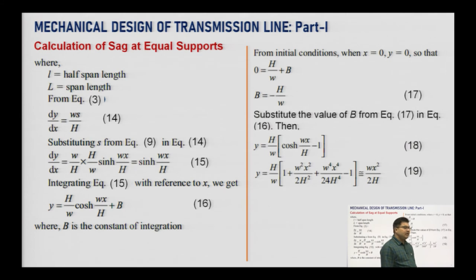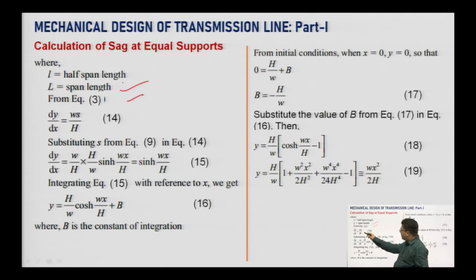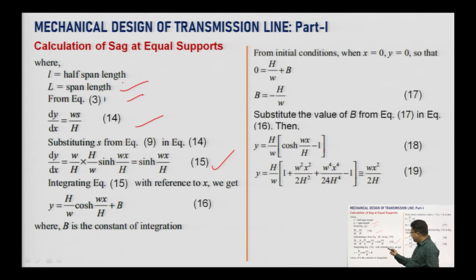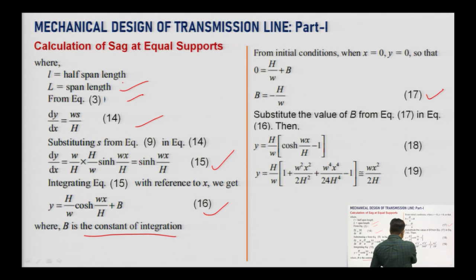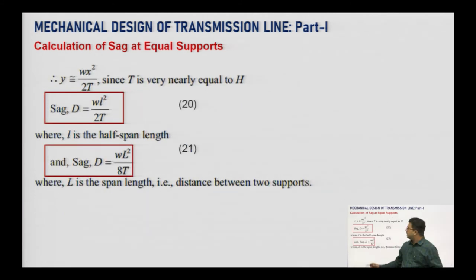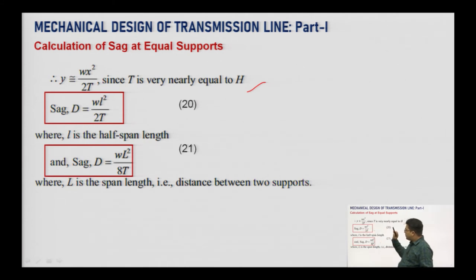From these equations, substituting and integrating with respect to x, we get y = w/(2H) · x² + B, where B is the constant of integration. Applying initial conditions (x → 0, y → 0) gives B = 0. Therefore, y = wx²/(2T), since T ≈ H. The sag d = wl²/(2T), where l is the half-length of the span. For the full span, equation 21 is used. This is the fundamental sag formula for equal-height supports.